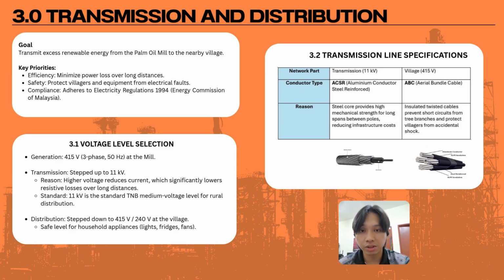For the physical infrastructure, we selected a specific conductor for each section. For the 11,000 volt transmission line, we use ACSR, aluminum conductor steel reinforced. The steel core provides necessary strength to span long distance between poles. For the village distribution, we switch to ABC, aerial bundled cable. Since these lines run near homes, the full insulation prevents short circuit and protects villagers from accidental electric shock.